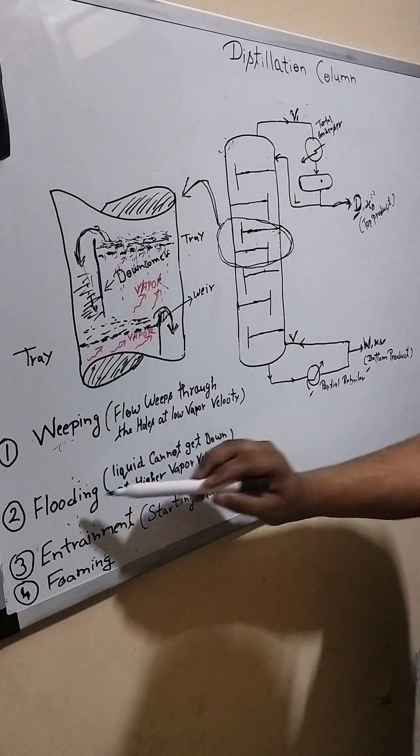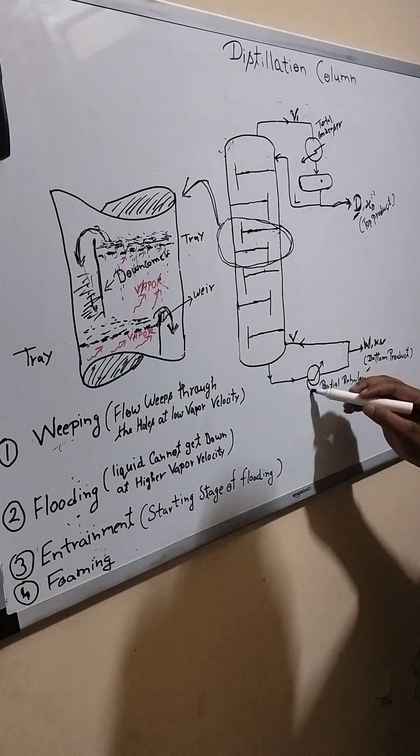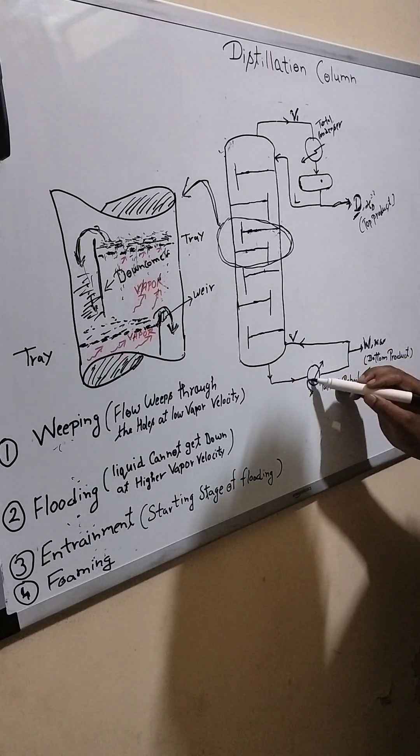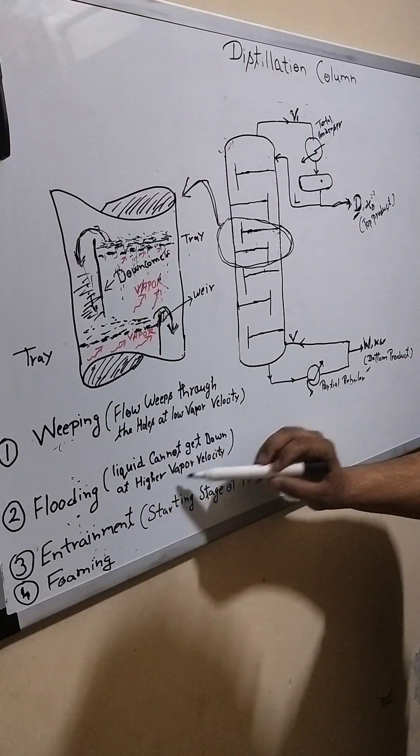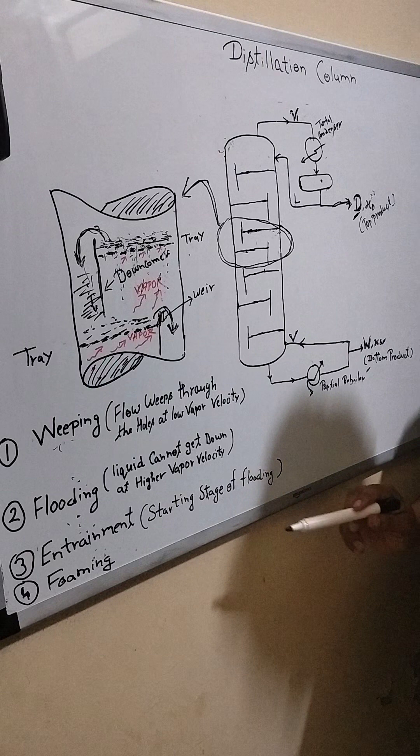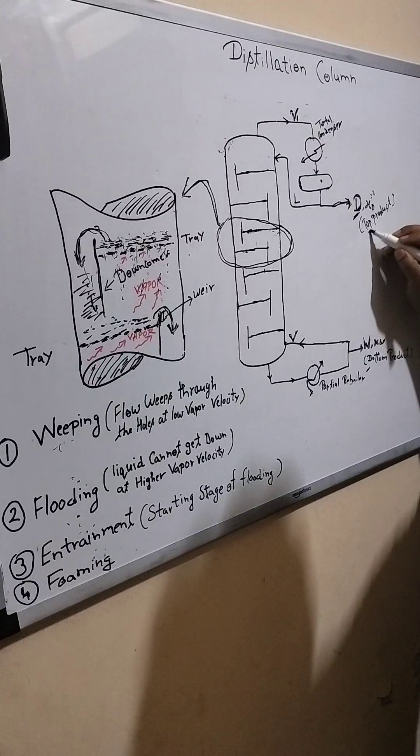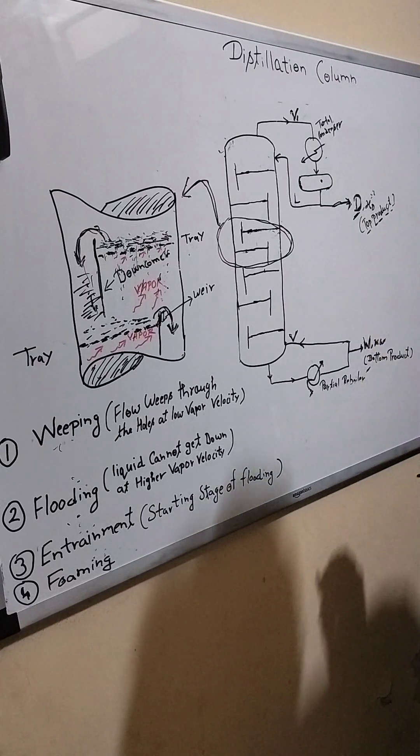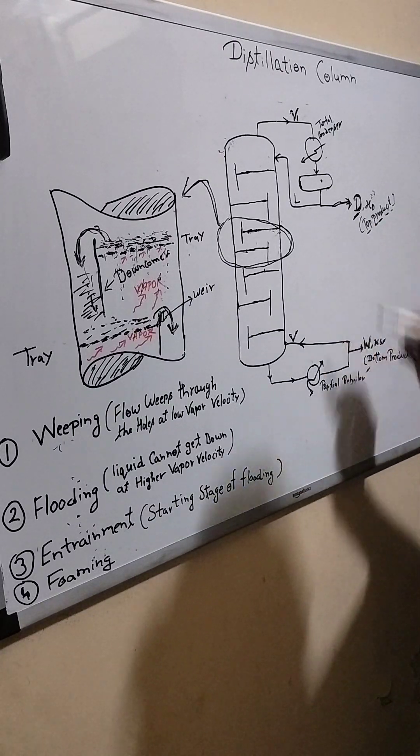So the reason of flooding may be your steam is very high. You have to see if your steam is very high. Liquid cannot get down at higher vapor velocity. So in flooding situation, you will get top product with low grade. The quality of top product will not meet your specification which you require during the running condition.